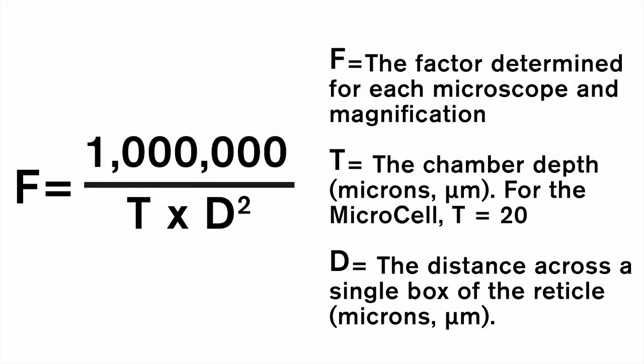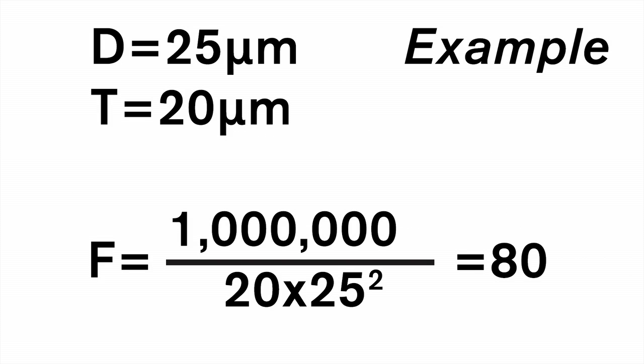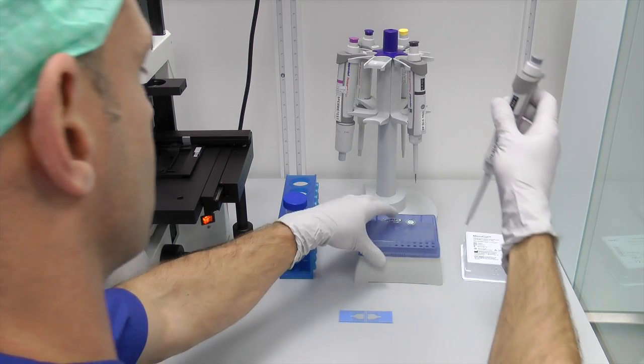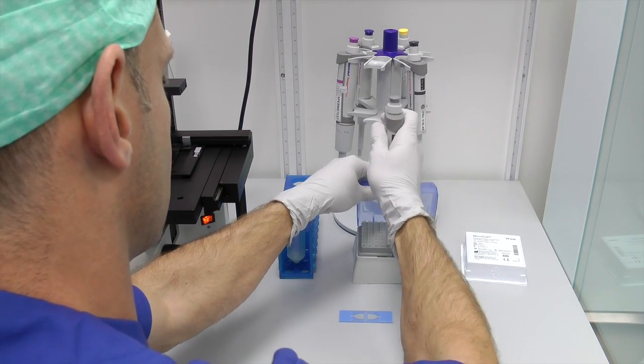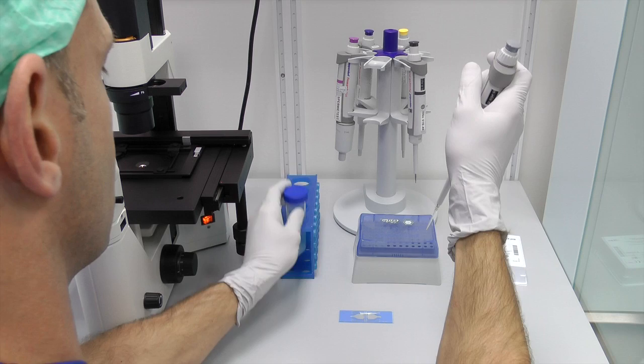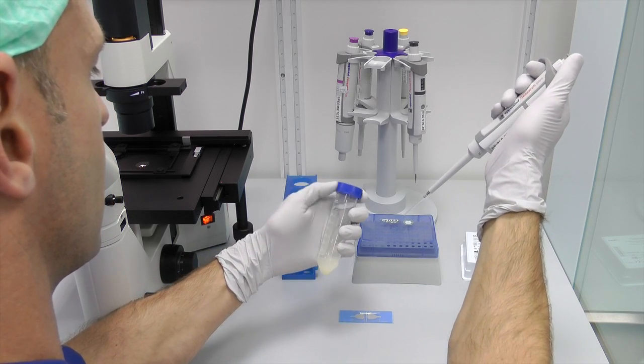Here is the formula for calculating the f-factor. Here is an example of how to determine the f-factor: d is measured to be 25 microns and t, the chamber depth, is always 20 microns. Then f equals 80 for that specific magnification. Place approximately 3 µL of liquefied semen sample into the clear loading zones. For the 4-chamber design, use 2 µL.